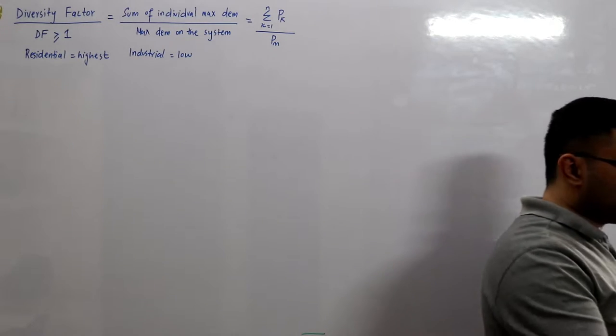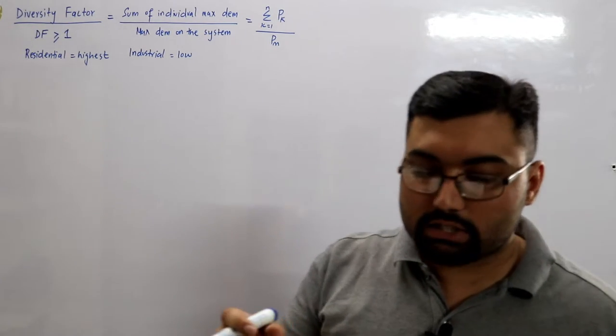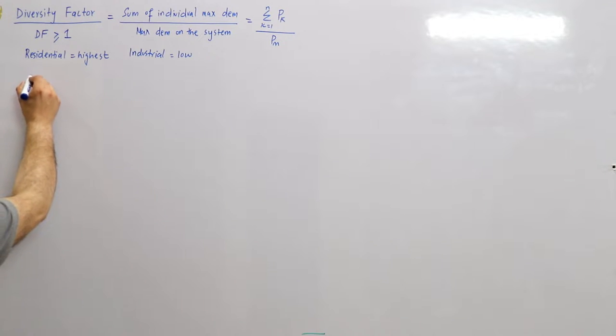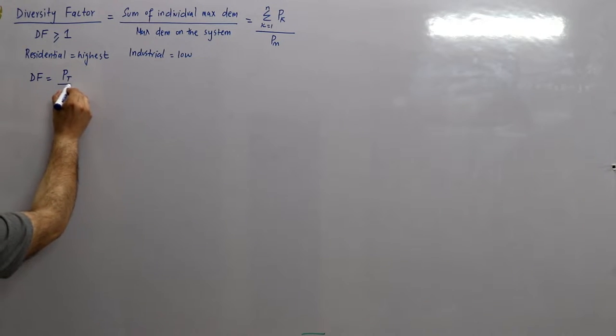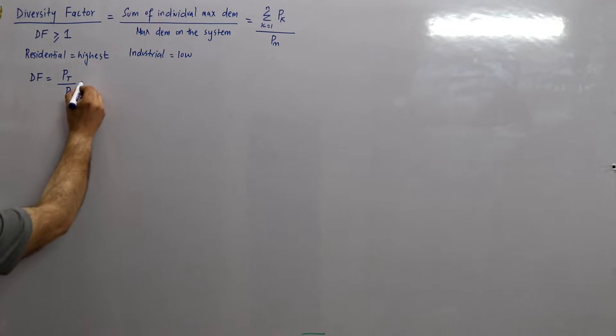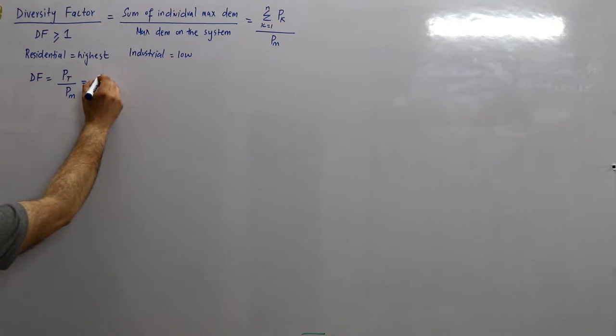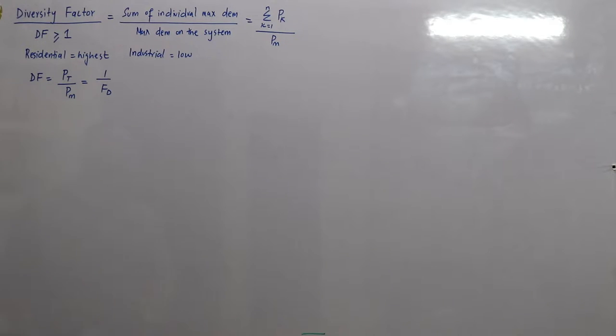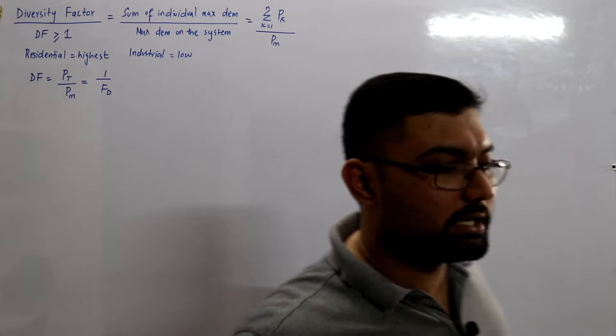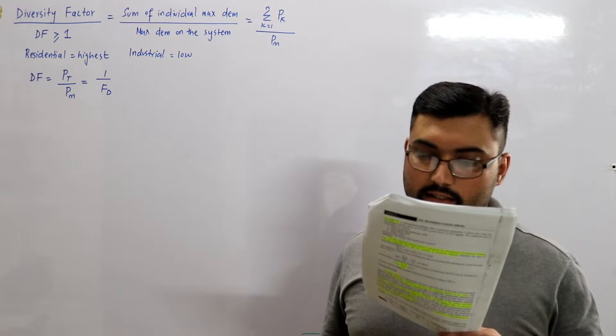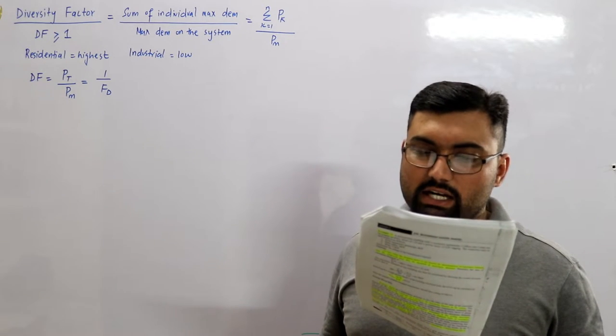The diversity factor is also defined as the installed capacity — or connected load — to the maximum demand ratio, which is the reciprocal of the demand factor.